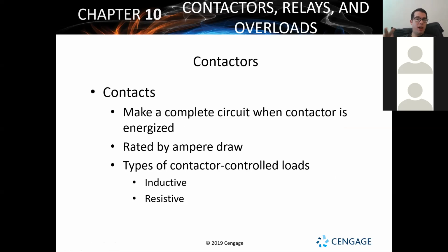So if you check and you've got 240 volts at your outdoor disconnect, and then you go to your contactor and you've got 120, you've lost 120 volts between your disconnect and your contactor. You've lost voltage. You've got to go find out where, why, or how it got away. Usually it's a damaged wire, it's fuses, stuff like that. That's super simple and basic, but it happens all the time.